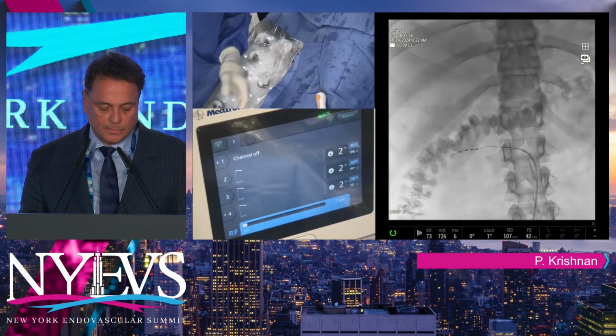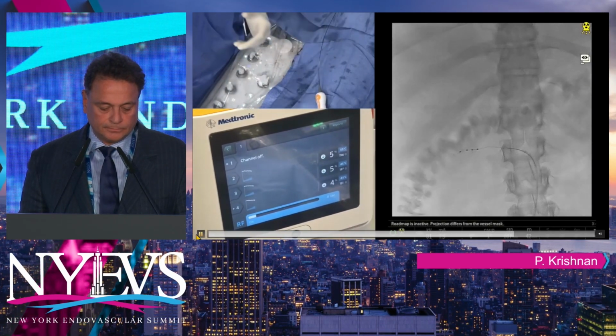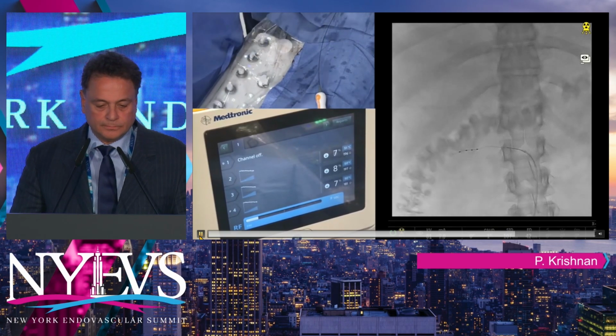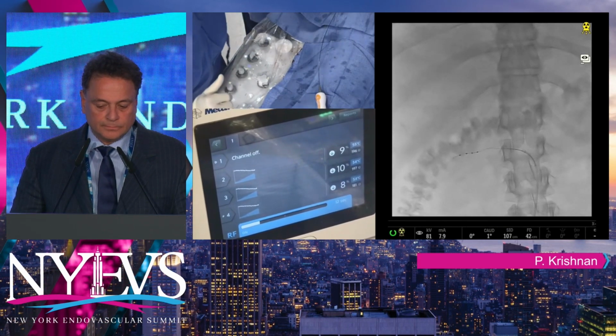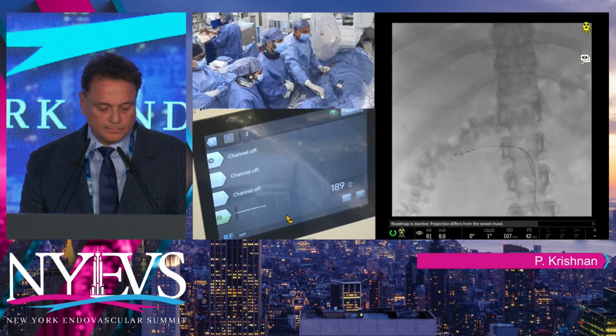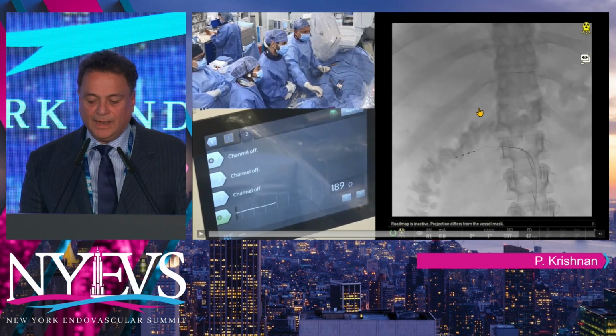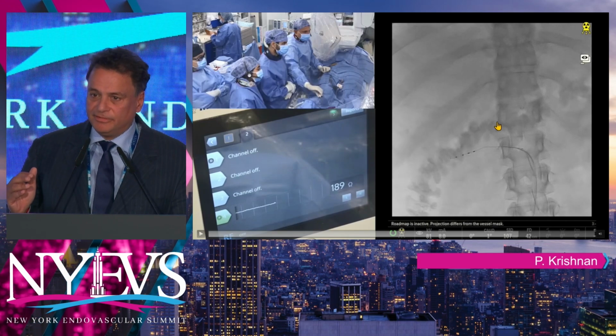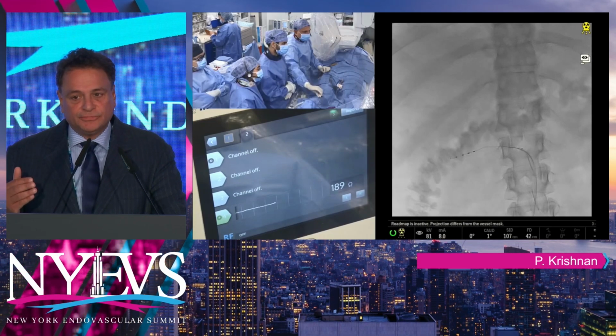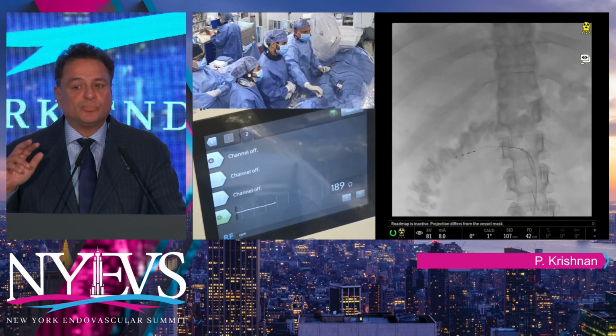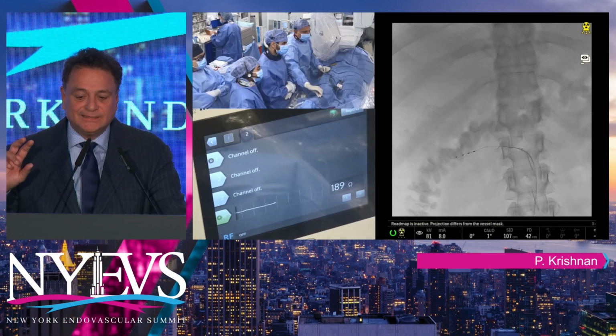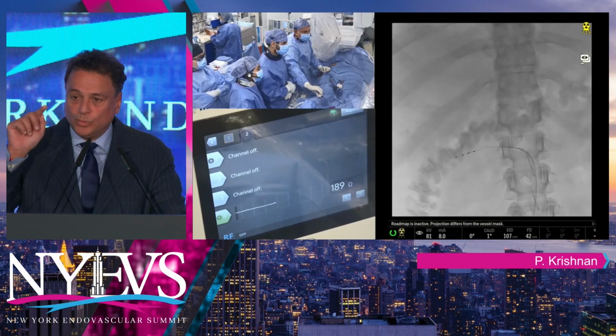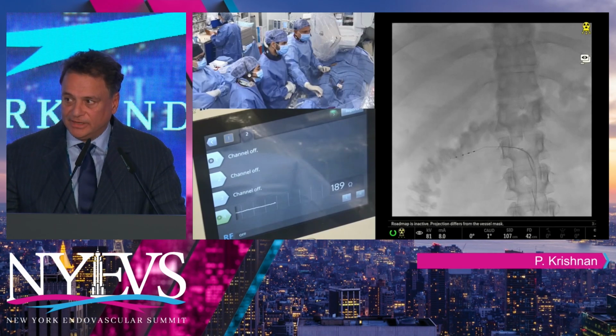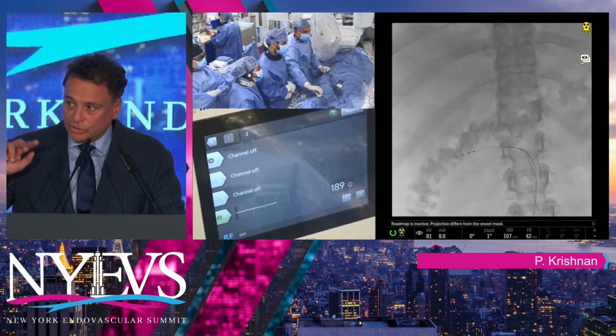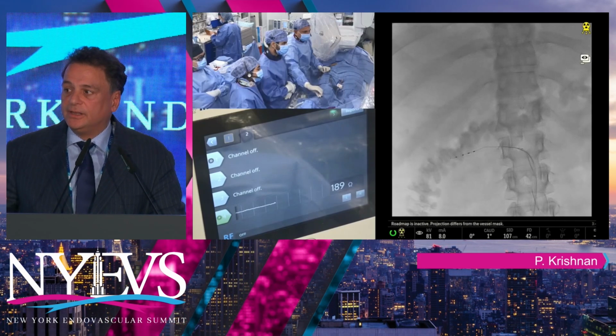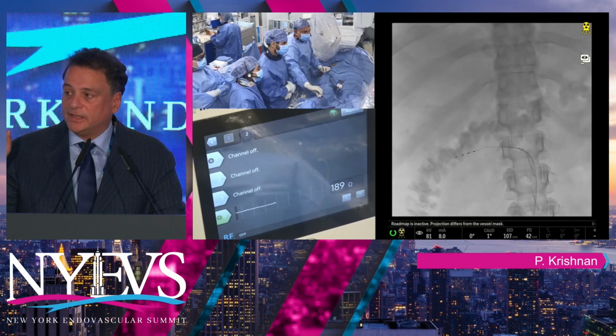Now, as the spiral catheter is doing the denervation portion, the machine itself is doing a lot of the work. Giving the sedation to the patient beforehand is super important. So we're just going to treat in 4. What I'm going to do is just rotate it slightly like that. What happened there was the impedance fell off and the catheter shuts off. When the impedance falls off, the reason is there's inappropriate contact with the vessel. At that stage, you look at which lead loses contact with the vessel, and then you go ahead and turn off the ones that have treated, and then repeat the treatment at the level of where the contact was lost.